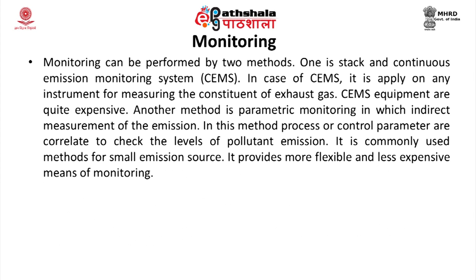Monitoring can be performed by two methods: the stack method and the continuous emission monitoring system (CEMS). CEMS is applied to an instrument for measuring the constituents of exhaust gas; CEMS equipment is more expensive. Another method is parametric monitoring, in which indirect measurement of emissions is used — process or control parameters are correlated to check the level of pollutant emissions. It is commonly used for small emission sources and provides a more flexible and less expensive means of monitoring.